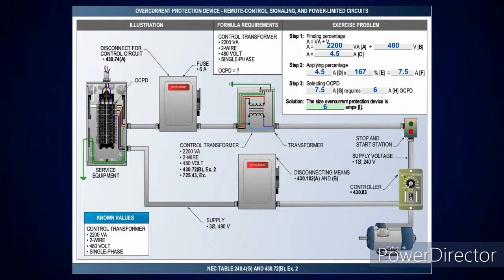And this is a single phase transformer, 240 volts, or 480 volts, I'm sorry. And we're going to take the 2200 VA and divide it by 480. That's going to give me 4.5 amps. I go over and look at table 450.3(B).